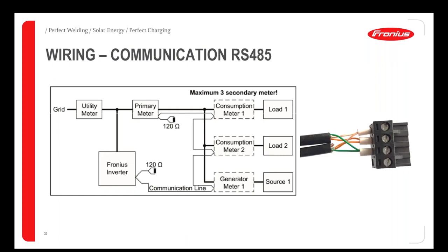And the installation for multiple smart meters, again, is pretty simple. So as you saw before, we have the 2 data cables, the orange and the orange stripe, and we have the green ground cable. Now all we're doing is crimping those into a bootlace ferrule, connecting into the meter, and then going to the next meter in the system. So it's a very simple daisy chain through all of the devices, making sure that we have the termination resistor on the first and the last devices enabled.